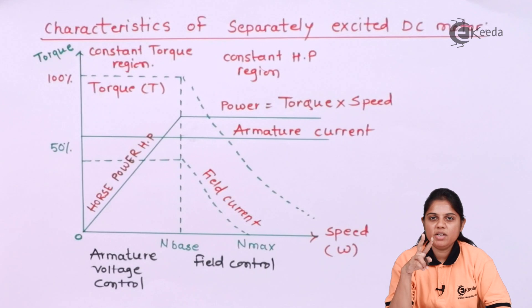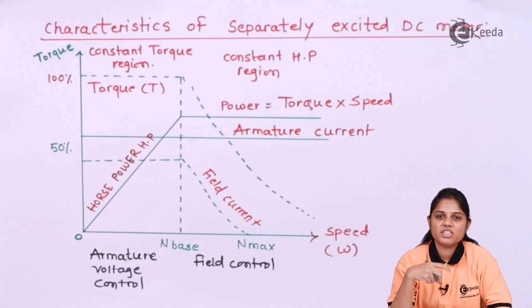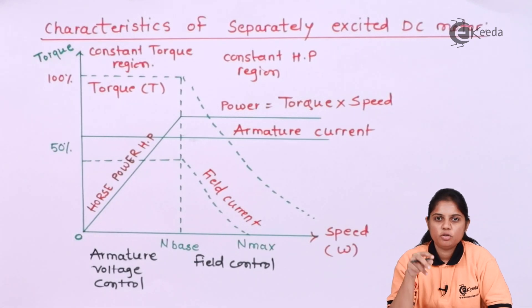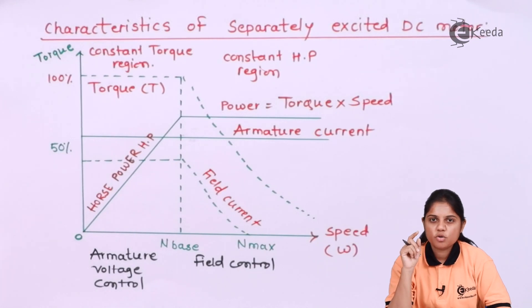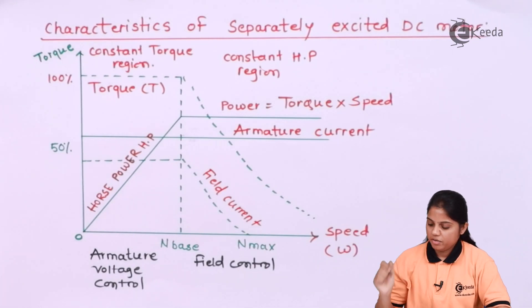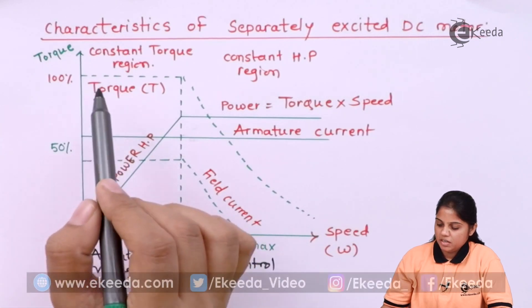Basically, as I mentioned, you can either change the armature voltage or change the field current to control the speed of the motor. This graph is divided into two sections: the constant torque region and the constant horsepower region.